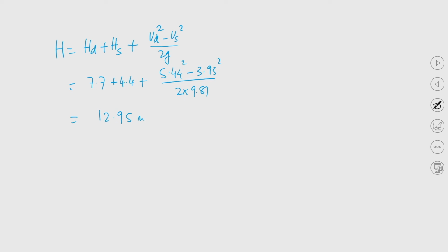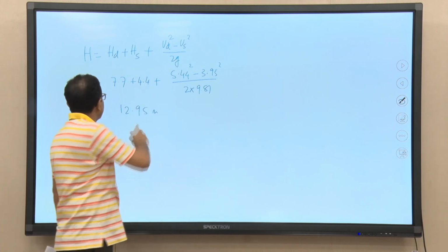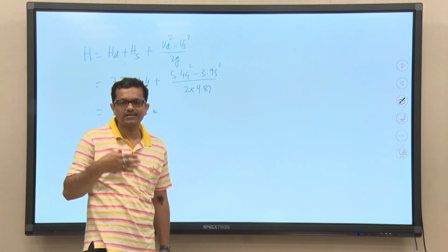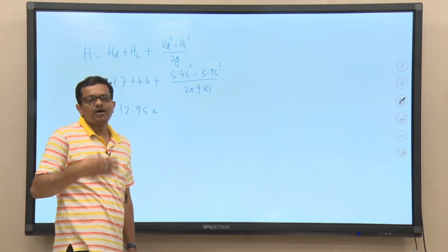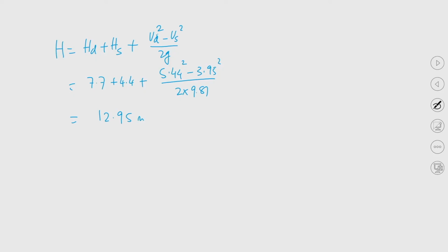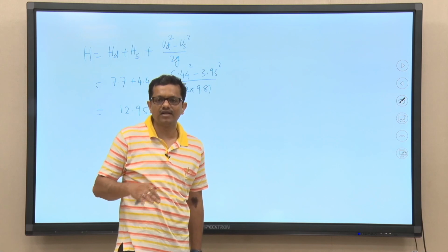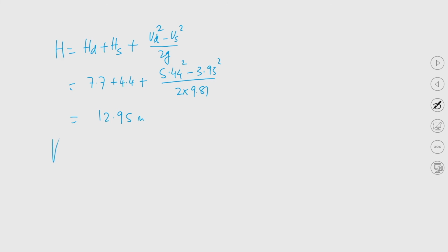Also, try to understand that suction head is very small as compared to the delivery head. That is the objective, right. If I recall correctly, in the previous class we discussed that the selection of the delivery pipe and suction pipe is done from two different perspectives. The perspective for the delivery pipe is to provide head, an economic consideration, and for the suction side it is to prevent the pump from the undesirable phenomenon, cavitation, right. NPSH available should be higher than, or at least equal to, the NPSH required by the pump. Okay, fine.